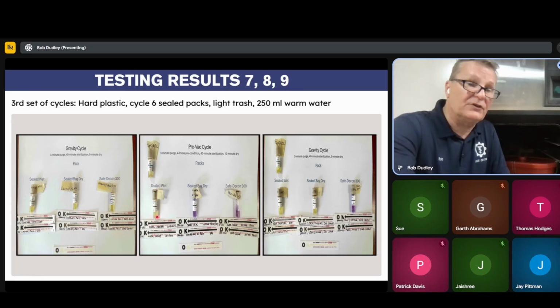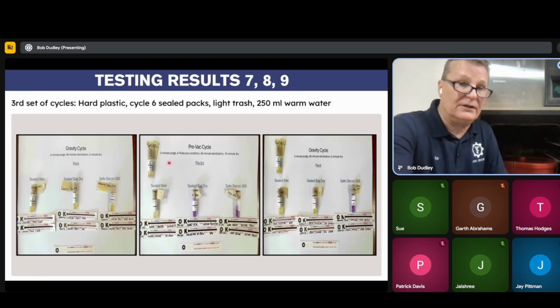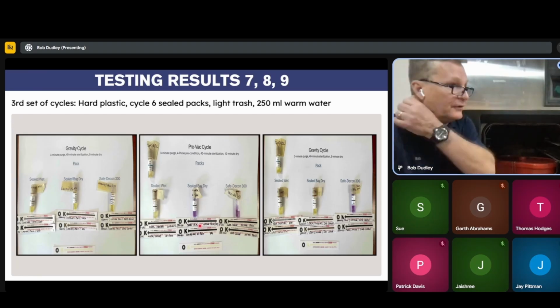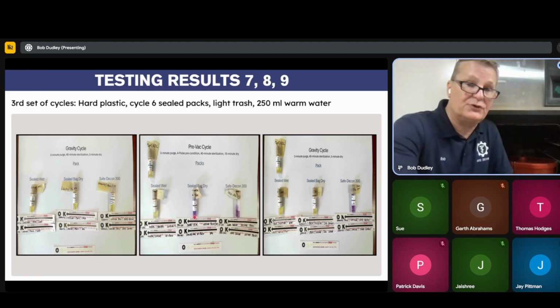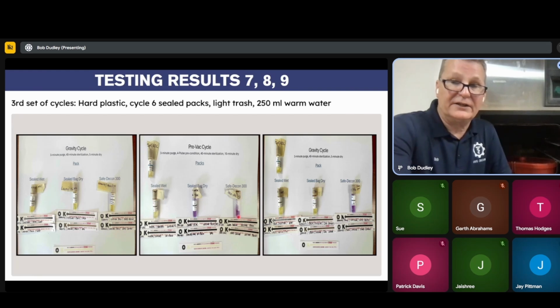Because when that valve opens up, by the time that water finally heats up and releases that pressure, you're going to get that boil, but it's too late. You're already going into the pre-vac. You're only going to get a very short burst of that steam and heat, not long enough to kill your biological indicator. Now here, the sealed dry bag did bust open. It must have opened during the time that was enough for the contents to get the exposure. The Safe-Decon, again, champ there. We got the kill on it.